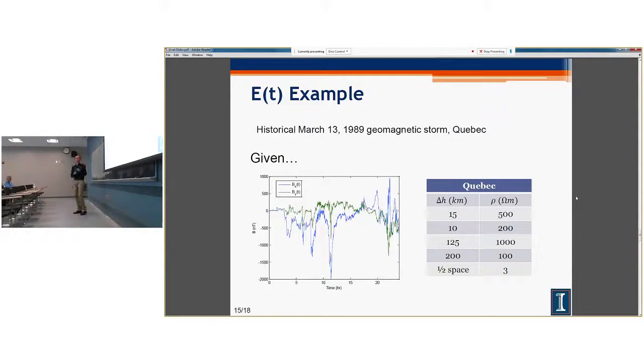And that was right at the time where literally the day I just finished this stuff. And so I plugged in my data, and I could pull the real-time data that just happened this past weekend off online. At that point, I was still copying and pasting. And I was able to view it, and it was really cool because we saw something similar like this, except an order of magnitude smaller than this, actually. But there was a huge spike right at the hour that their generator tripped offline.